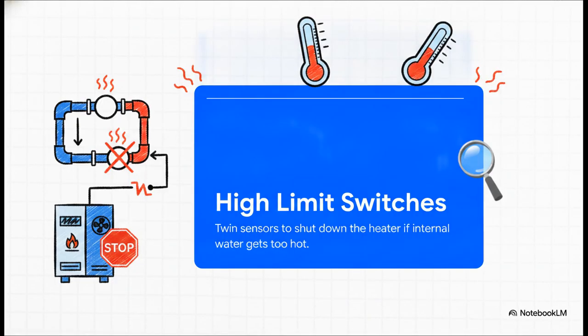The next gate is the high-limit switches. These are twin temperature sensors, usually set to 135 and 150 degrees. They're the ultimate failsafe designed to shut the heater down if the internal water gets dangerously hot. For instance, if your bypass valve breaks, the water trapped inside the heat exchanger can literally start boiling. These high limits will immediately trip to stop a total meltdown.